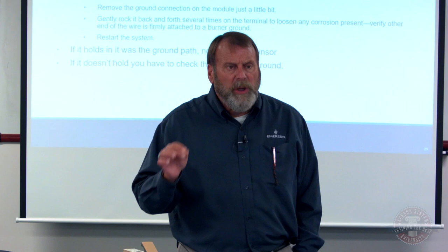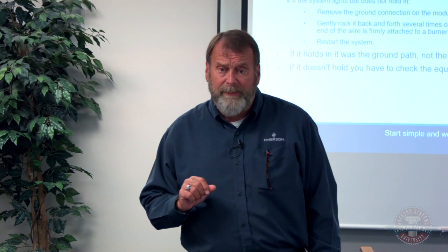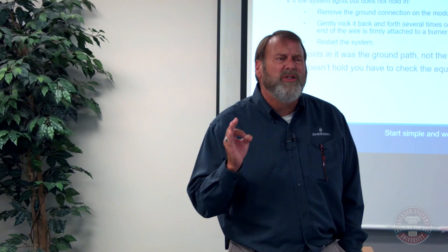We're working with a millionth of an amp, a microamp, which is nothing. You can literally have a film on your ground plane that is enough to inhibit electron flow. Just a film. And it won't burst through. It won't punch through. Now, you put 5, 10 amps on there, it'll burn through anything. But a microamp, you can't even see the corrosion occurs.